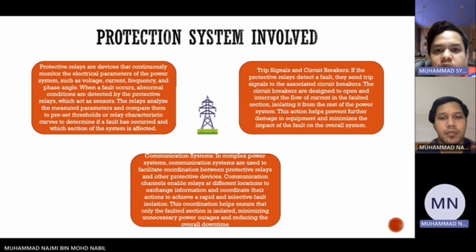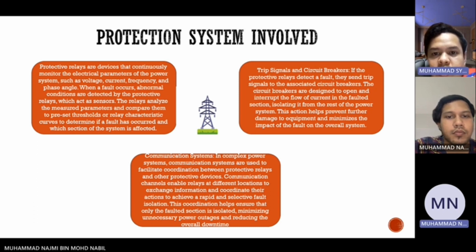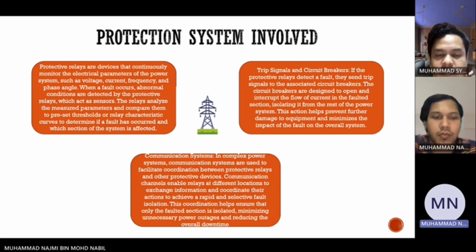Okay, number two, trip signal and circuit breaker. If the protective relays detect a fault, they send a trip signal to the associated circuit breakers. The circuit breakers are designed to open and interrupt the flow of current in the fault section, isolating it from the rest of the power system. This action helps prevent further damage to equipment and minimizes the impact of the fault on the overall system.